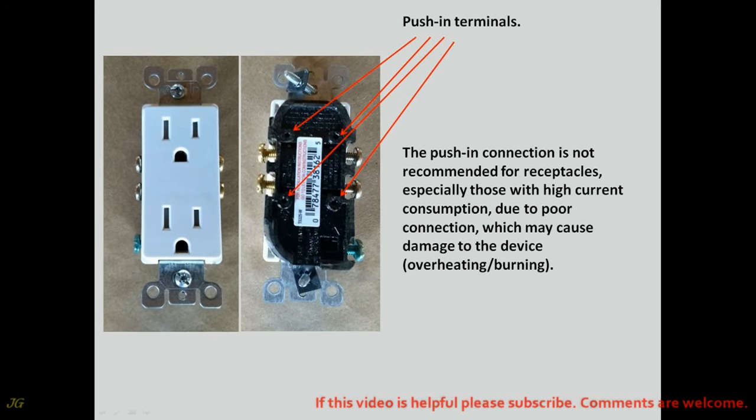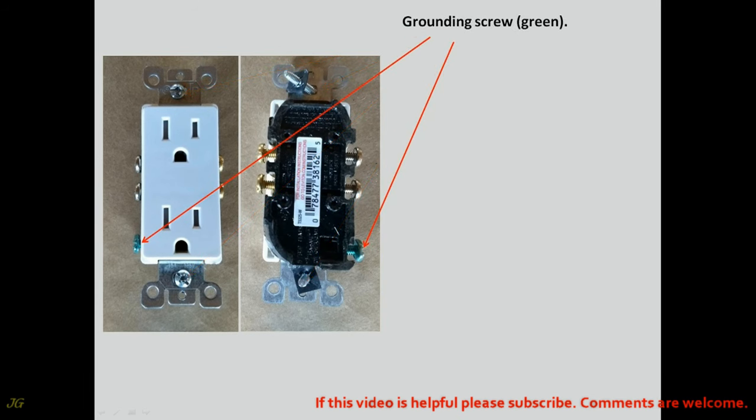The push-in connection is not recommended for receptacles, especially those with high current consumption, due to poor connection, which may cause damage to the device, overheating, burning. Receptacle mounting screws. Grounding screw, green. Neutral screws, silver. Hot screws, gold.